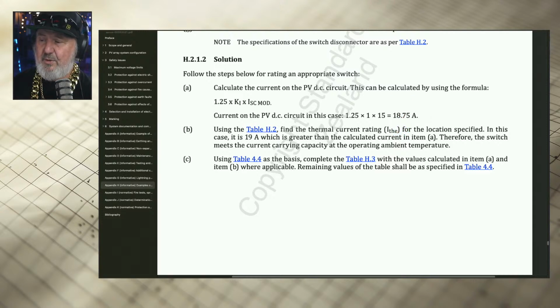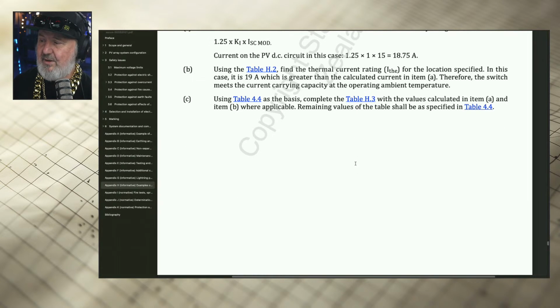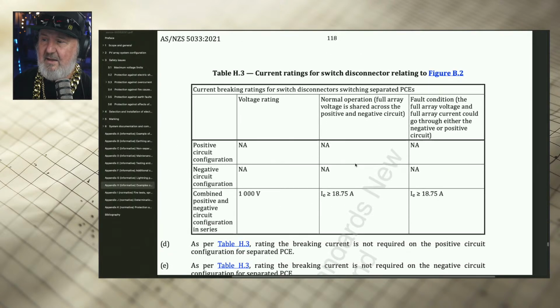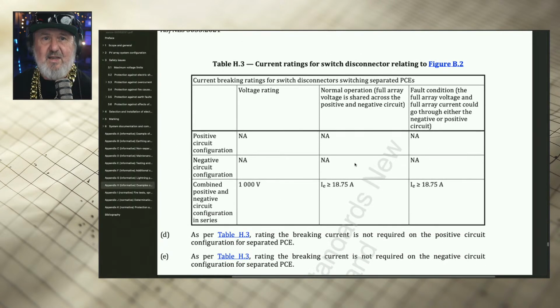So we use Table H.2 to find the thermal current rating. And let's have a look. We'll go down here. Because this is a separated inverter, there is no positive circuit configuration or negative circuit configuration that needs to be considered, because they're combined. That means they're breaking both the positive and negative at the same time. And so the voltage rating is 1000. As long as our continuous operating current is greater than 18.75 amps, we're all good.